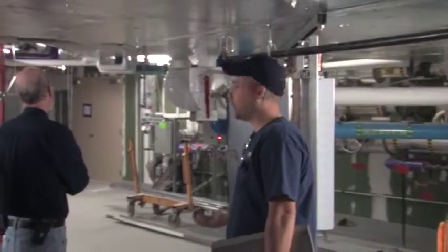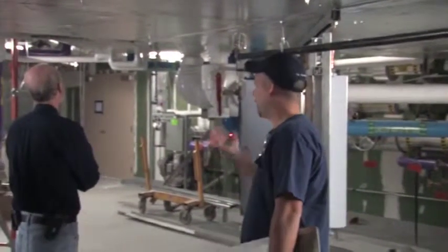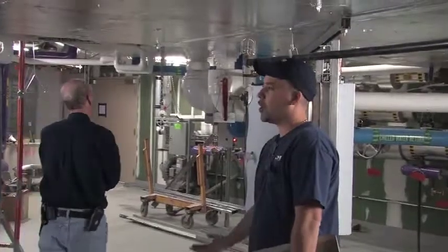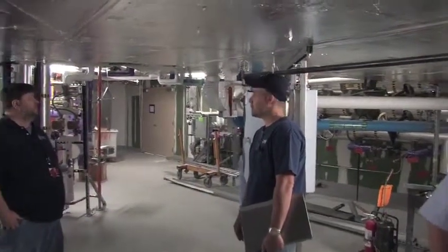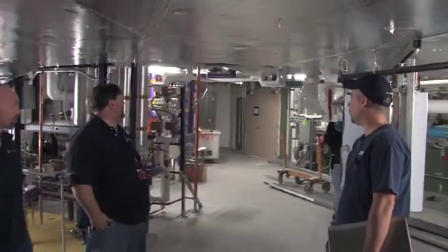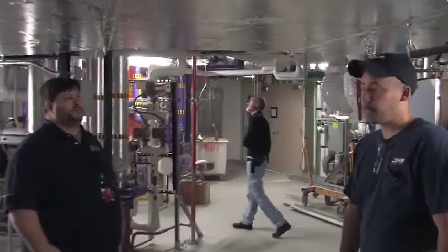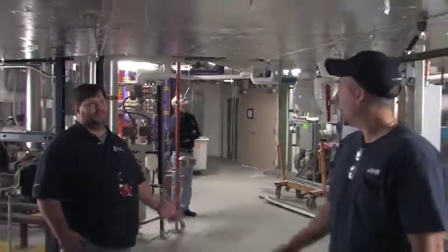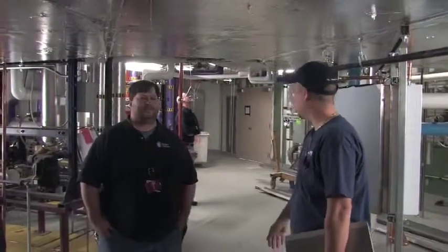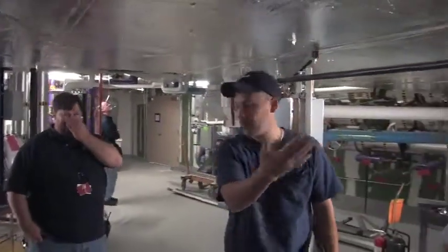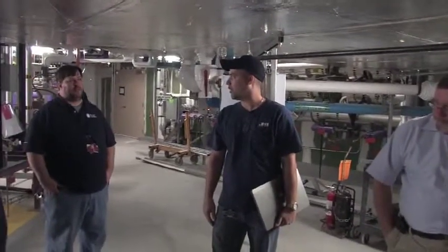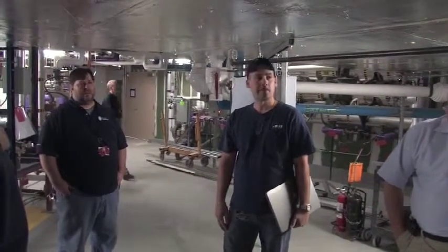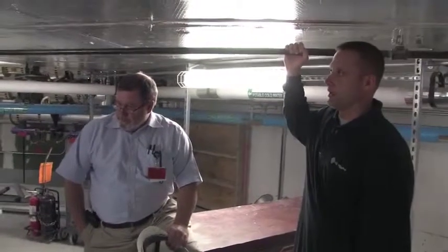If there's a fan failure, you'll get a fan alarm, and it just has a chill water valve. It's a modulating valve, not a two-position valve. So that's pretty much it for the fan coil unit. It's just mechanical on that side. That just serves this area over here, and the one that's down here just serves the ones above the Cabelco compressor. And the one in the sub-basement does the electrical switch gear downstairs.